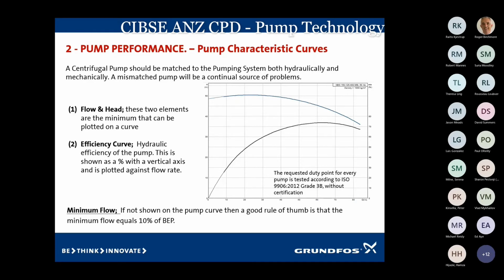If you are concerned about minimum flow, the last thing you want to do is run that pump against what we call a closed head for long periods. A closed head is zero flow. If you shut the valve off, the pump would be running at zero flow, and it would produce around about 50 meters head. That's a really good test if you want to see if a pump is actually working correctly, if it's running in the right direction, or to be sure that there are no issues with the impeller. If you shut the discharge valve, the gauge should read about 50 meters head, then you know that pump is working.